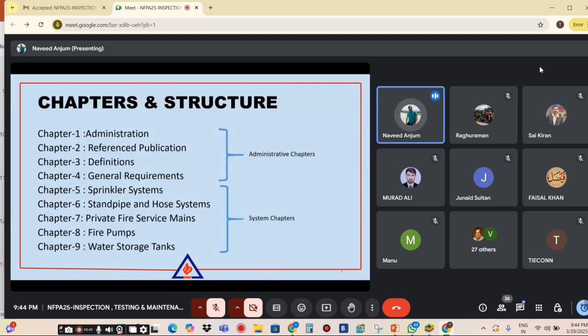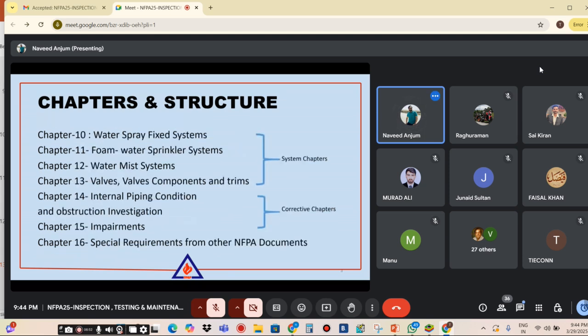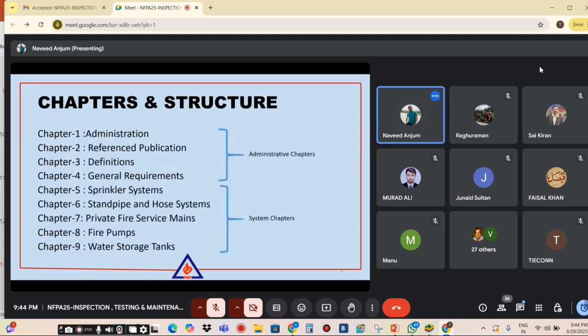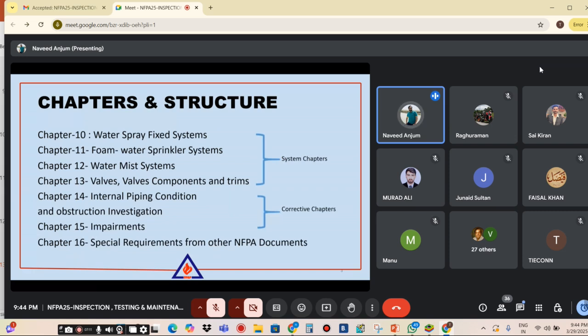So chapter number 5 to chapter number 13 are the main system chapters. And then there are some corrective chapters. Some chapters discuss different systems like sprinkler system, standpipe system, private fire service mains, fire pumps, water storage tanks, water spray fixed systems, foam systems, water mist system, and valve and component trims. And in the corrective chapters, they discuss internal piping condition and obstruction investigations, and also impairment procedures.